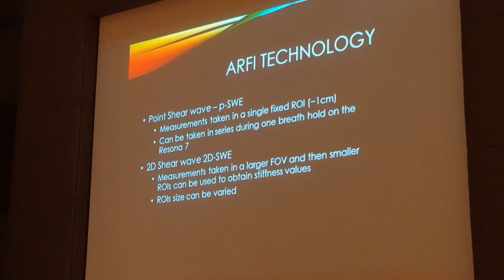And this can be taken in series in one breath hold on the Resona 7, and we can maybe demonstrate that during a break. The 2D shear wave is measurements over a much larger field of view, and then smaller ROIs can be placed to obtain liver stiffness values. And in this one, we can change the ROI size to average more of the liver. So here's a representative image of a point shear wave, and we're going to talk about where to put the box and how to do the study shortly.